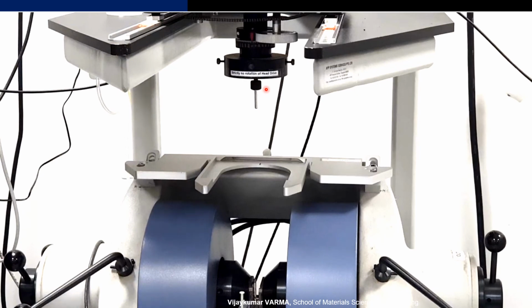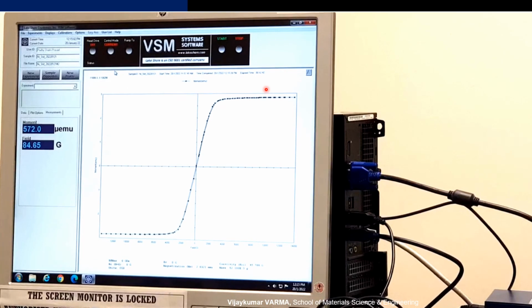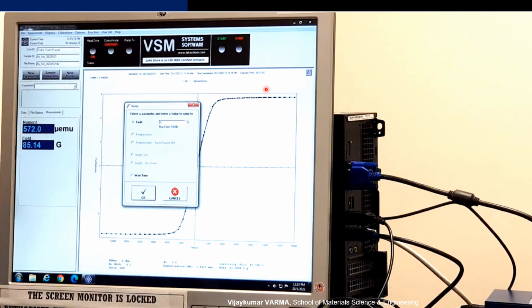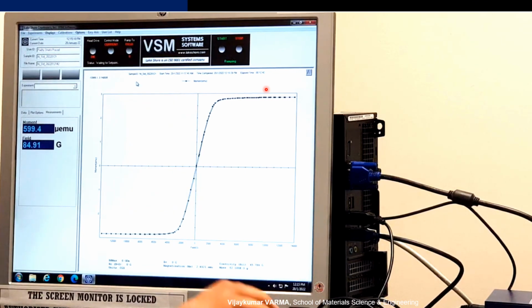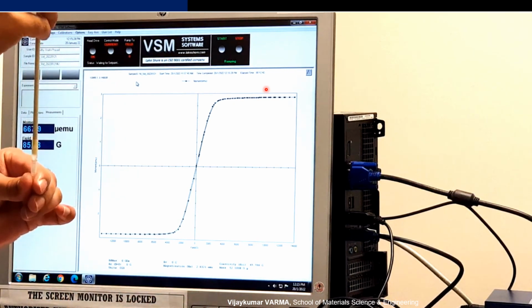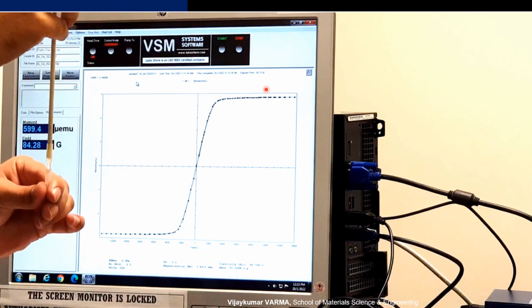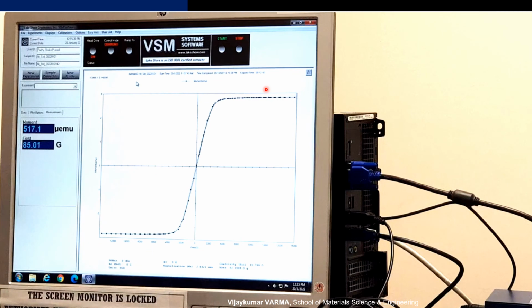Remember, we will always keep the head drive on when the experiment is completed and the blank is mounted. Again, just to be on the safer side, I'm ramping current and field values to 0. And removing the standard from the sample holder and keeping it back.